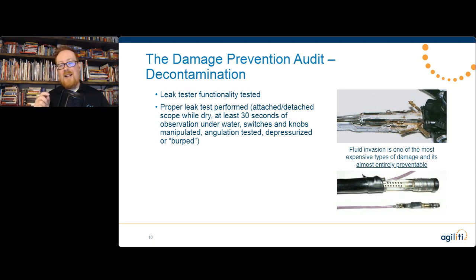You need to check that the hoses are attached properly, that there are no holes in them, and that they actually are pushing air like they're supposed to. You'd probably be very surprised at the number of times we go to a facility and the facility says, hey, we keep getting fluid invasion in our scopes, but we leak test them, so we don't know where it's coming from. And you go to their leak tester and you push the button and stick your finger on the hose, and sure enough, no air's coming out. So no air means no leak, right? So it's not telling you anything. So know what your leak tester needs to be able to do its job properly, and ensure that it is functioning also.